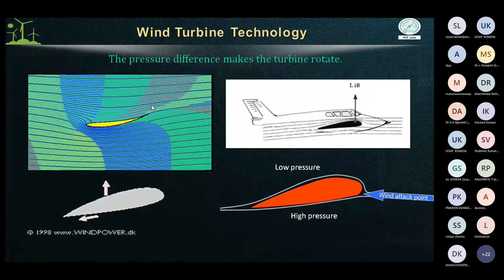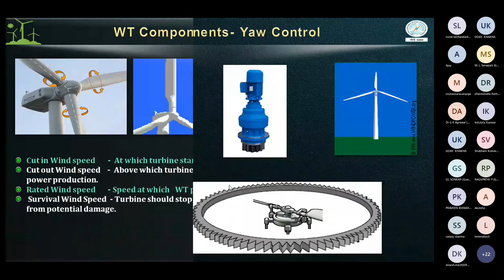So I was telling about the yaw control here. There's a yaw control, a yaw drive, between the tower top and the nacelle. This is used basically because wind is dynamic in nature. Wind speed may be 5 meters per second, and after some time it will be 10 meters per second, and after some time it will be 0. So it varies all the time. Wind direction also changes all the time. It may come from the east, then suddenly change direction to west or south. So the blade has to face the wind for the lift force to take place and make it rotate.